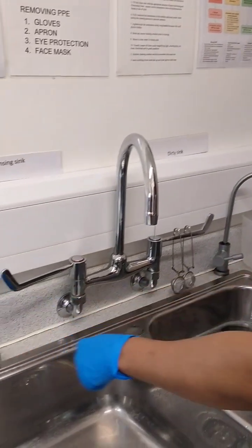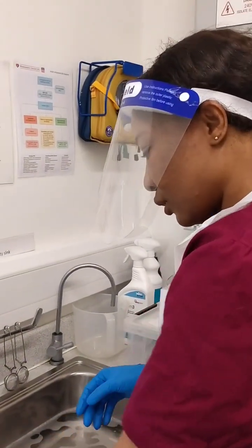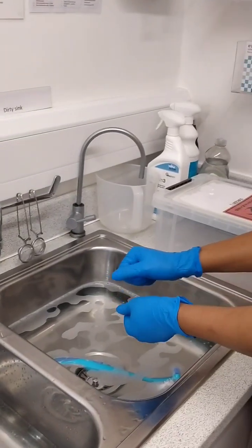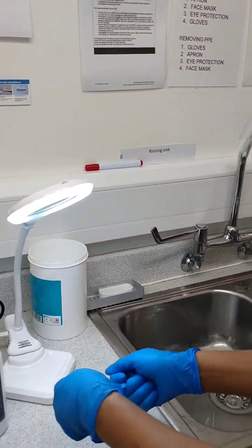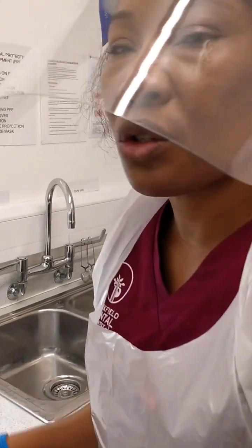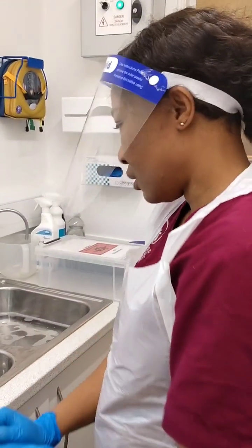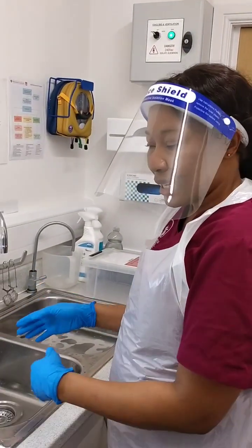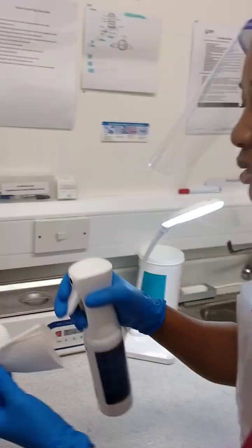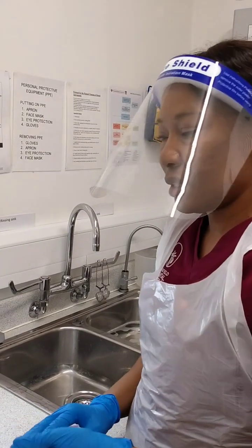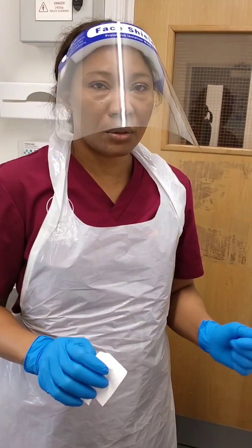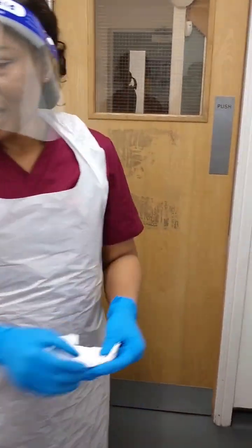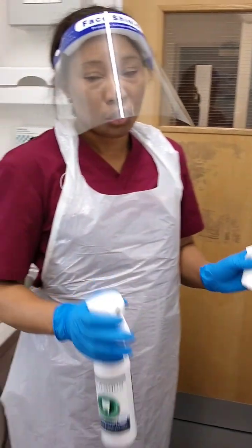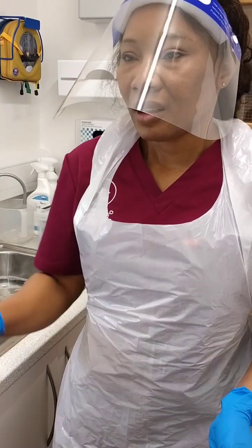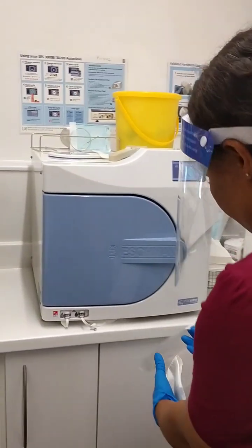It's 10 mils, and we put it in. Next, we run the rinsing water again on the other side of the dirty sink. So we scrub our dirty instruments, and then we rinse them, check them, put them in the WD, and then they go into the autoclaves. Again, we clean the dirty side by spraying and wiping clean all our surfaces. And when we do that, we take all our gloves and PPE off, and then we put on new ones, and then we spray again and wipe all the clean area, just as we did on the dirty side. When we do that, we turn on the autoclaves here, and we turn it on here as well.